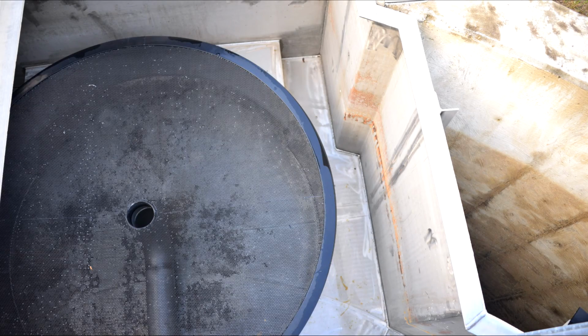Once flow reaches the top, water passes over and through the screen, trapping solids greater than the mesh size. The water level rises through the screen and the siphon begins to prime. As the top water level is reached, the siphon discharges and the backwash cycle is complete. The solids are washed to the center and discharged through the central overflow pipe.